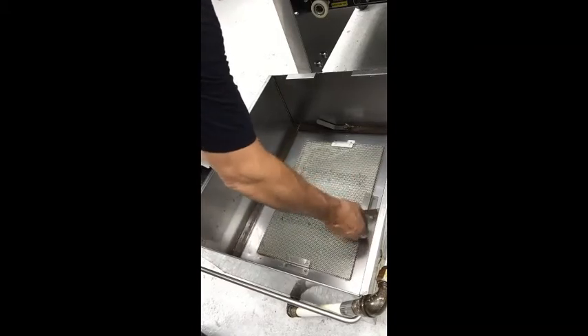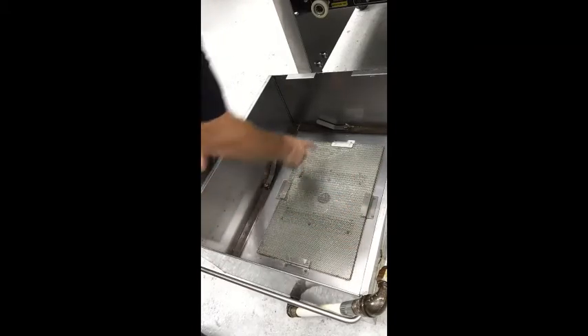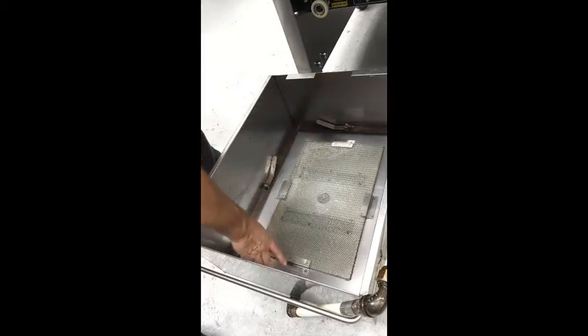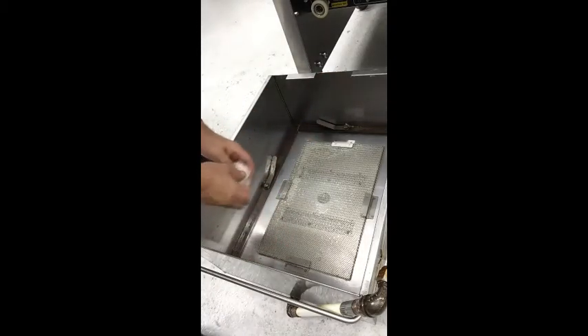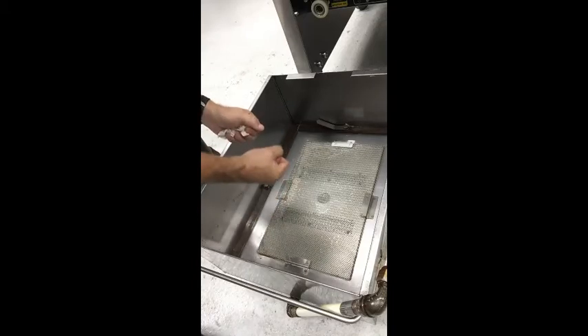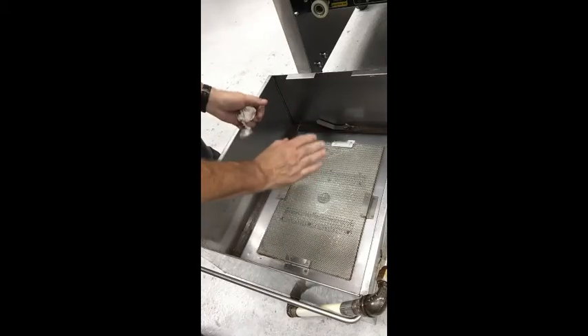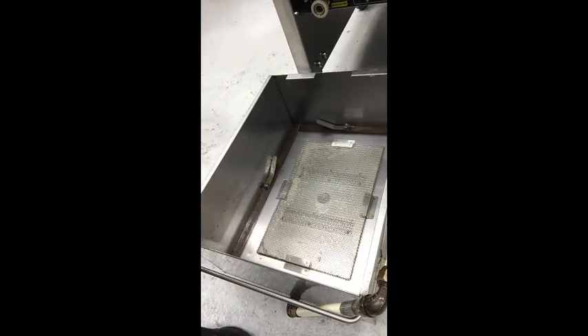You have 4 of these latches for preventive maintenance. You definitely want to go ahead and make sure all of these are intact, and make sure that when we put this in, you'll see here in just a second that they latch down good and snug. Otherwise, it'll allow that debris to get down around the paper.